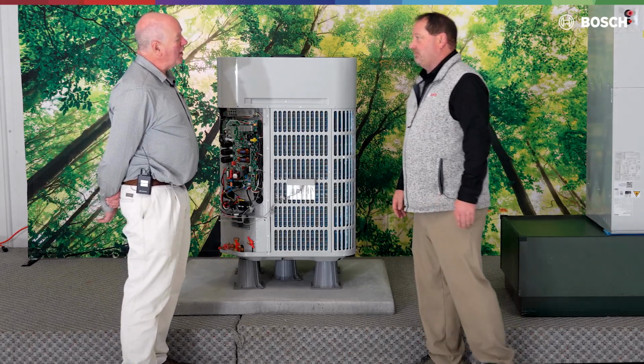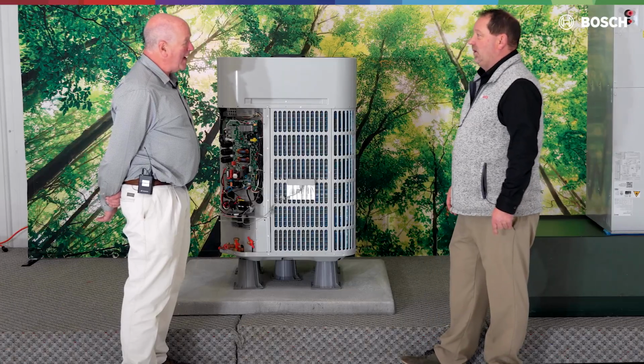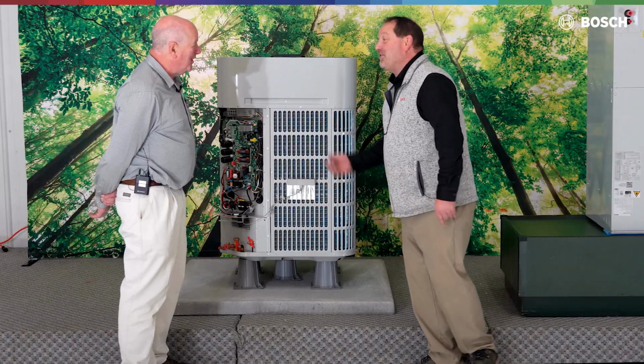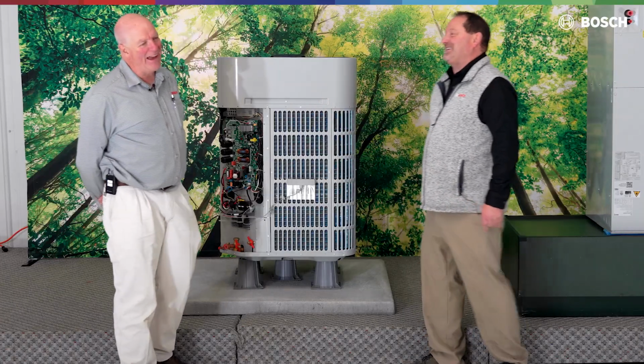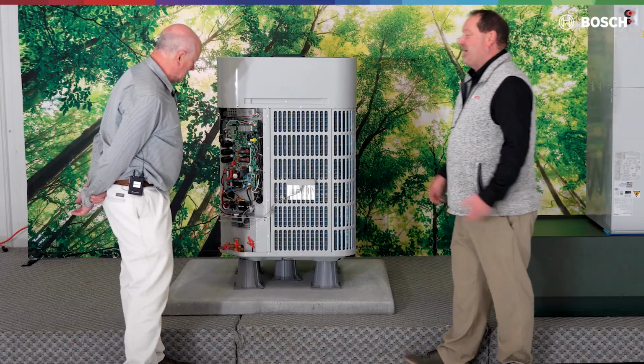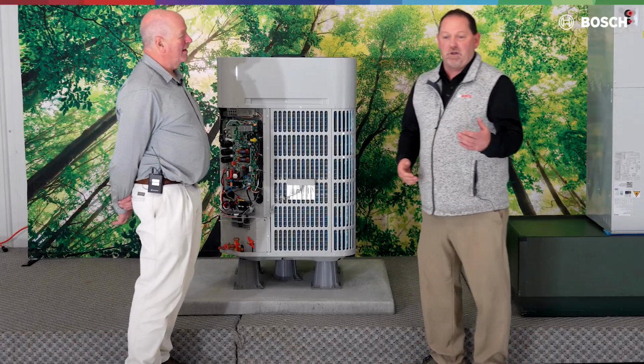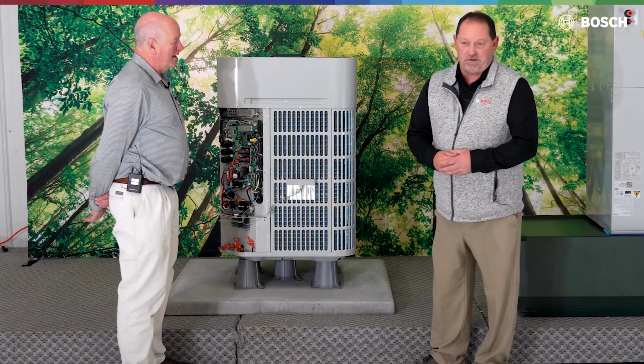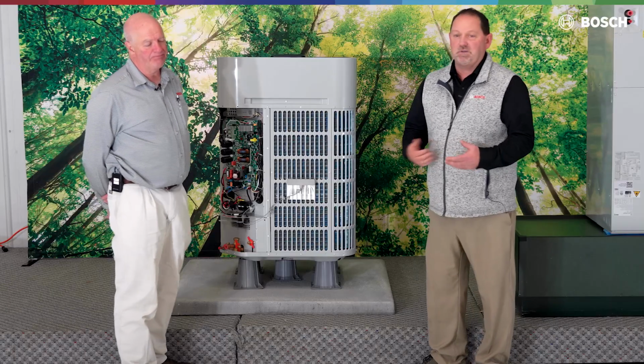So Chris, we've got 3 options on liquid line, correct? 3/8, 3/8, or 3/8? No, just one option, just 3/8. Just a 3/8 liquid line. Oh my gosh. If we've got a 1/4 inch line or a 1/2 inch line, we're going to need to replace that line set. We have no choice but to replace it.